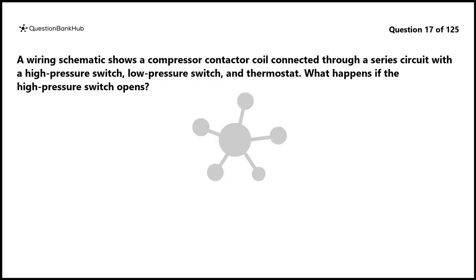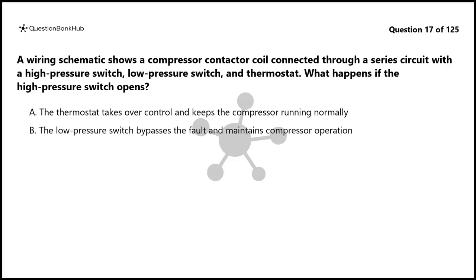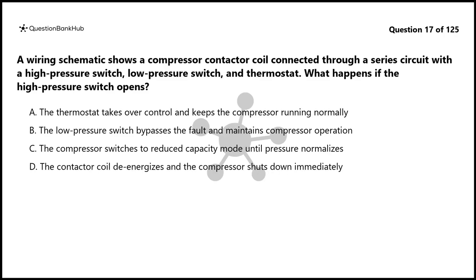Question 17. A wiring schematic shows a compressor contactor coil connected through a series circuit with a high-pressure switch, low-pressure switch, and thermostat. What happens if the high-pressure switch opens? A. The thermostat takes over control and keeps the compressor running normally. B. The low-pressure switch bypasses the fault and maintains compressor operation. C. The compressor switches to reduced capacity mode until pressure normalizes. D. The contactor coil de-energizes and the compressor shuts down immediately.